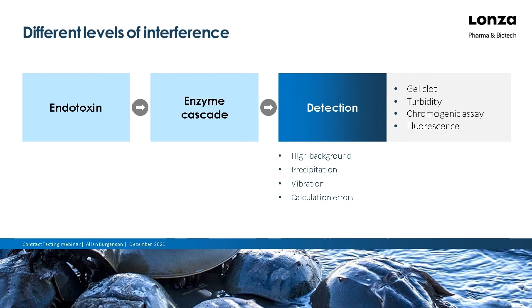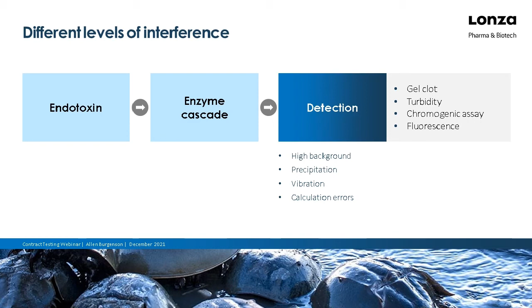For detection, if you have a very high background of endotoxin, it will be very difficult to recover a low level of spike in your endotoxin. So you're going to have to dilute out closer to your MVD with such a high background. You can have precipitation, and vibration also is not recommended for doing an LAL assay because it interferes with the gel clot formation or turbidity formation. And you also have calculation errors due to lab issues that you have to be aware of.